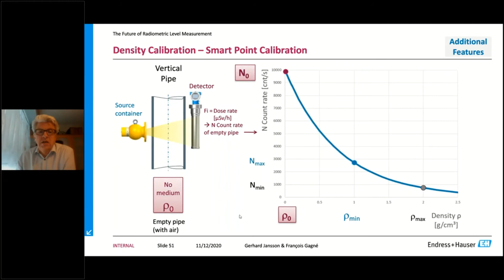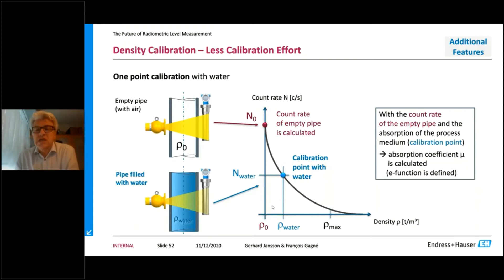The new style is doing it with what they refer to as a smart point. So we still need to calibrate one point. And usually the easiest is to fill this pipe with water. The other point is with the pipe empty. And this could very well have been done first of all. And now we will have this E function curve between those 2 points that will lock the curve. So when I later on do my measurement, I will have this curve to follow, this E function, and I will then have down here my maximum density without actually having to calibrate this. So this is a significant improvement because I only need to have one liquid, and typically that would be water, and water is very often, at least in the mining applications, equal to 1. So it's a very simple calibration procedure.